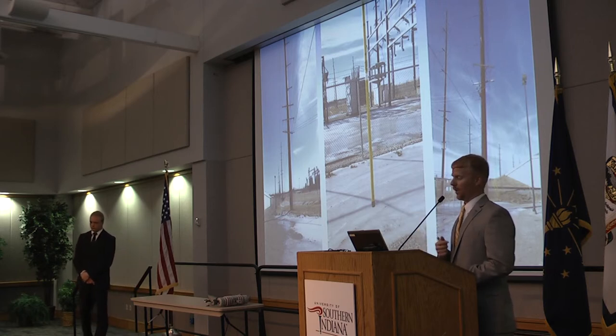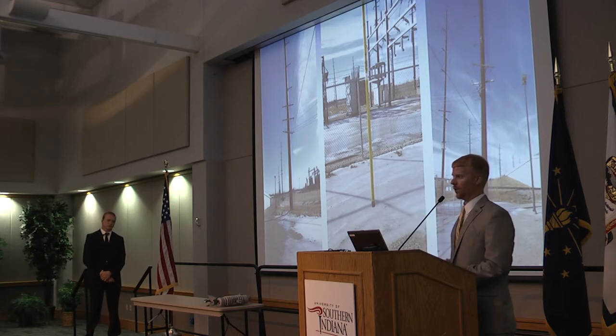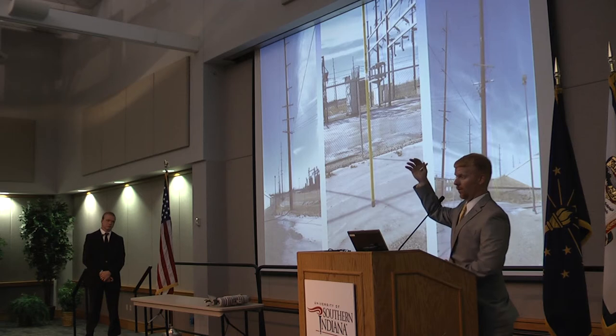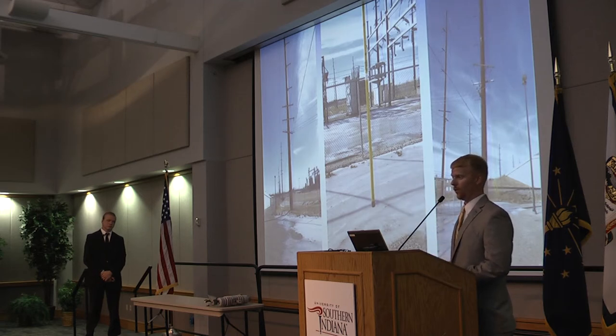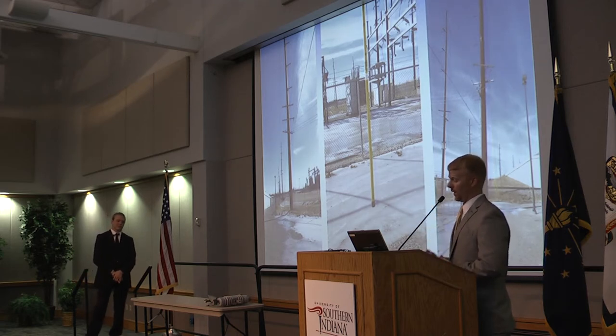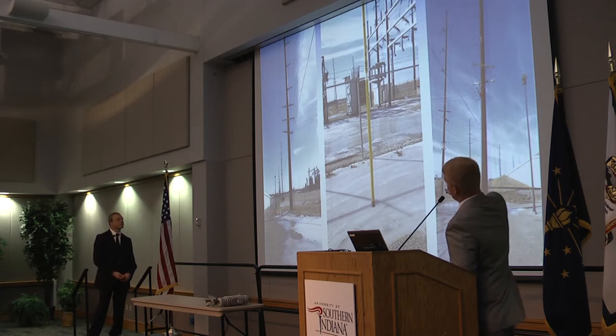When you have a 45-foot pole, you bury into the ground 10% plus 2 feet. So with that, you end up with a 38.5-foot pole above ground that can actually connect. So I use a 45-foot pole in that location, and that's how I know which size pole I need. These are the transmission lines, the distribution on the bottom. This is 69,000 volt up top, and this is 12,000 volt in these areas, and these are the poles that are located right outside the substation.